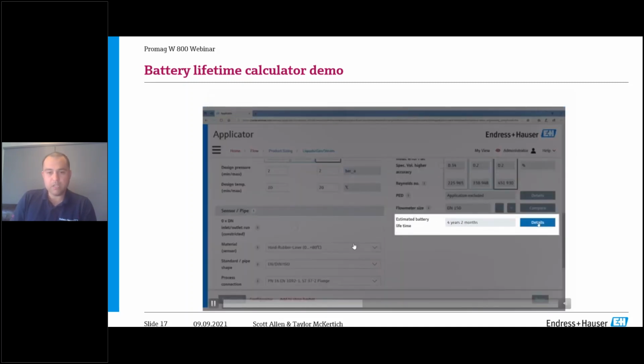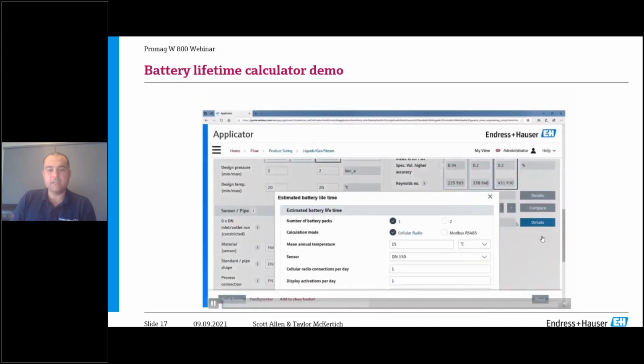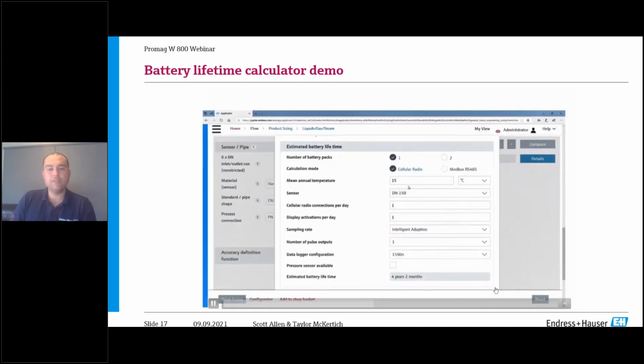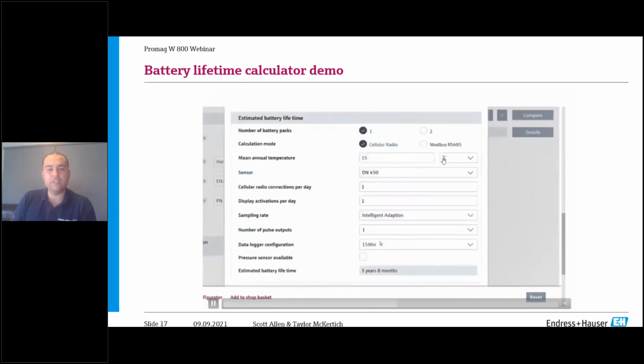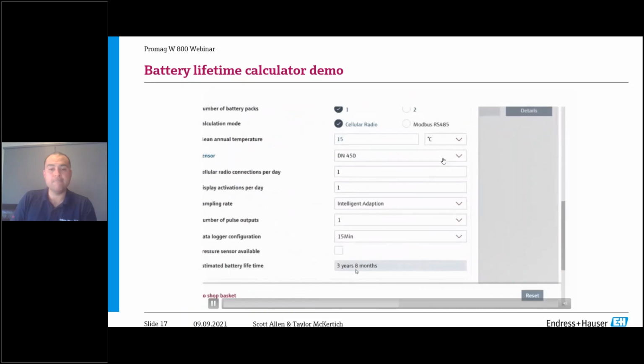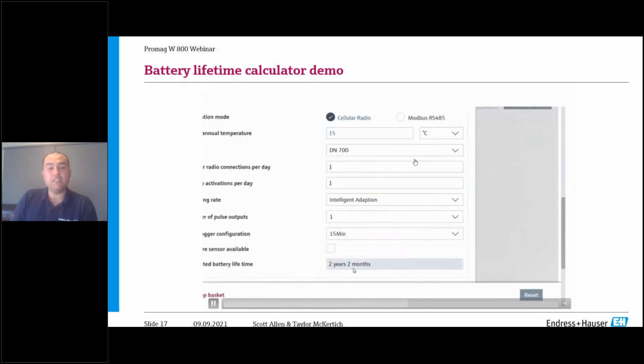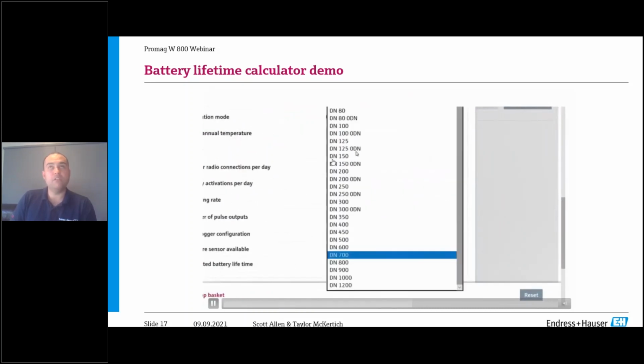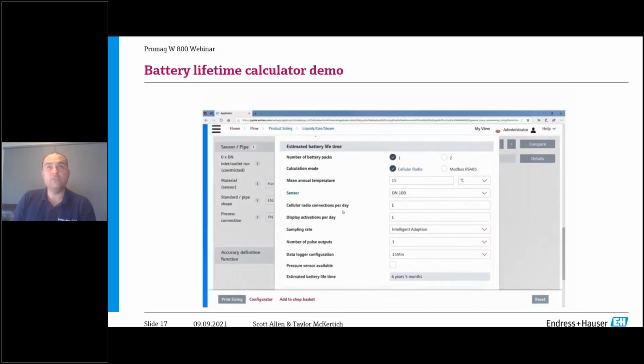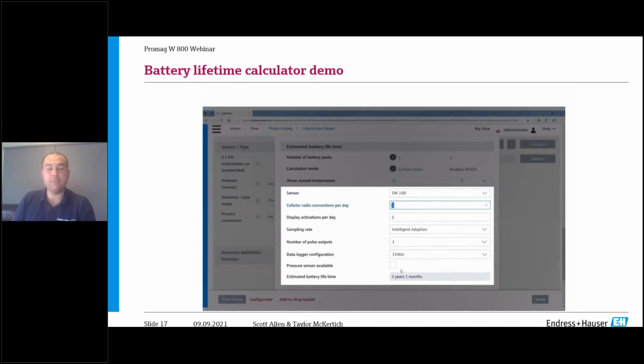With this tool you also get an estimated battery life function. You enter how many battery packs you have, whether it's one or two, internal or external, the size of the flow meter, the output you're using—cellular or Modbus—and the measurement frequency, like how often you're logging. All those factors impact battery performance and lifetime.